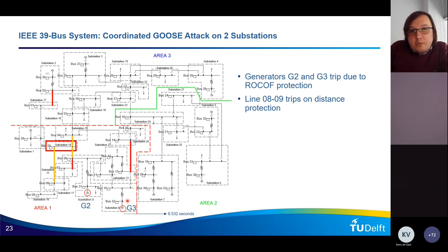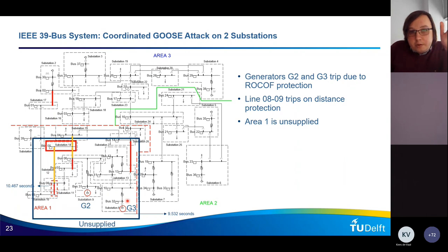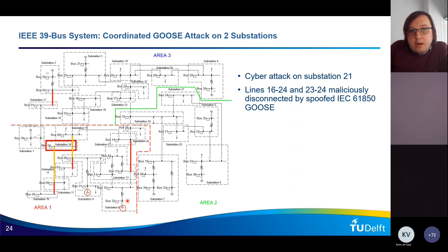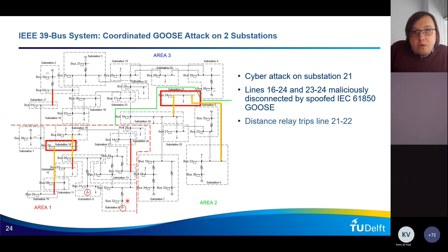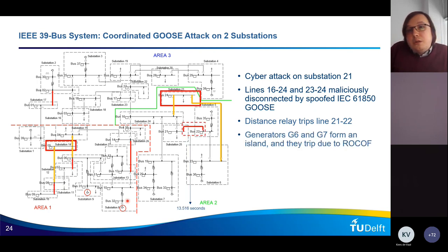Line 8-9 trips also on distance protection. So same observed phenomenon, and then area one becomes unsupplied. Now, in our scenario, we assume it's a distributed cyber attack across the power grid. So nothing stops the attackers from conducting another attack on other substations that would result in two more lines being disconnected. So as a result, distance relay trips line 21, 22, and generators 6 and 7 form another island.